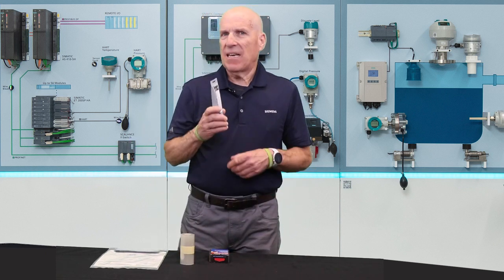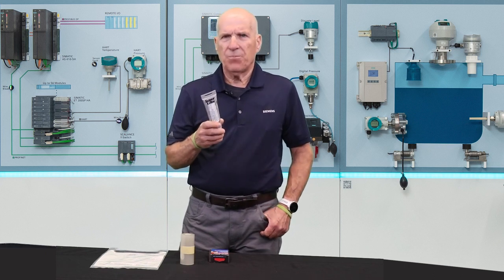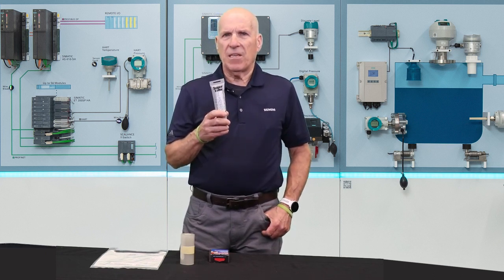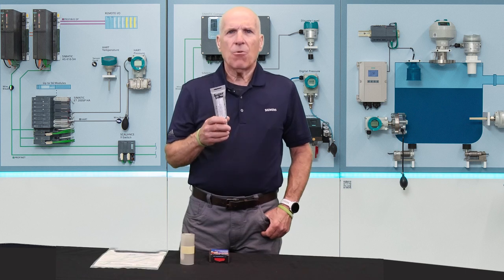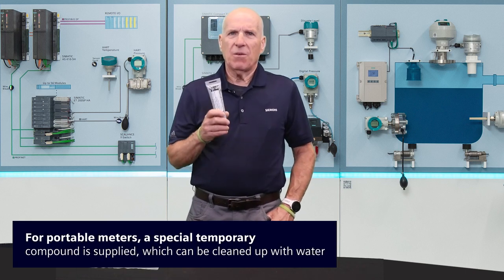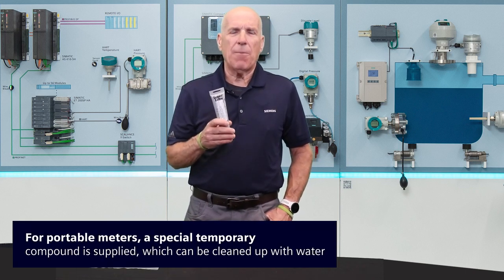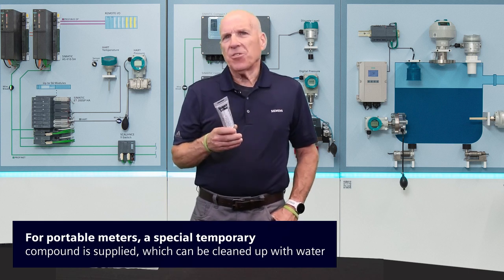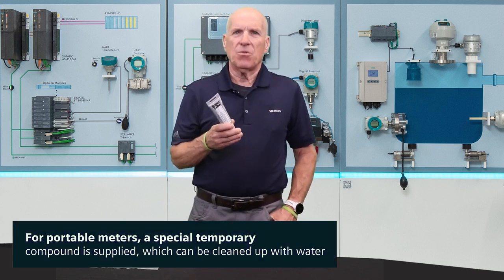Coupling compound is a necessity for all clamp-on flow meters. It's applied to the face of the sensor that contacts the pipe, creating an optimal path for the sonic energy to transfer into the pipe wall. Its function is similar to what medical teams use when they perform a sonogram.